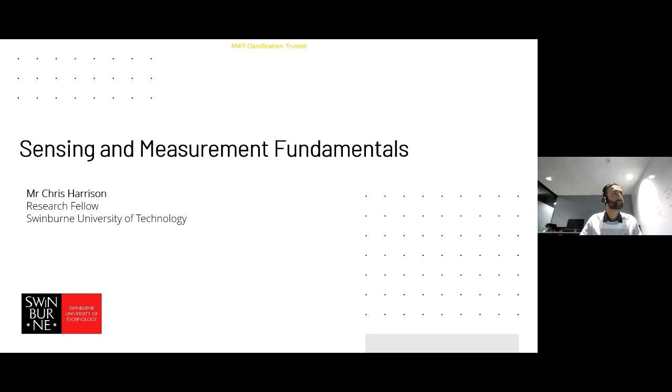So something that a lot of good thermocouple interfaces will do is what's called cold junction compensation. Because they know that the material coming into the box is going to be different from the copper, they can measure the temperature using another temperature sensor, usually not another thermocouple, but something like a PT100 or a resistive device, and then do the math to figure out what voltage offset to subtract away to get rid of the effect of that connector. In terms of how you know whether or not the thermocouple's working, you go back to good old calibration, right?